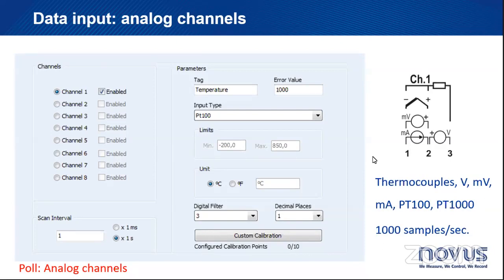Well, there are some cases where you really want fast action and fast response time. For example, if you're measuring pressure. Pressure is something that can change very quickly and you want to act on that. So you want to see any small changes. So you might not want a big digital filter on when you're measuring pressure, for example. And mainly depending on what type of sensor you're using, okay? So digital filter is that filter which is applied by the FieldLogger, okay? Decimal places is the quantity of decimal places you want to be stored and displayed, okay? Let's go to the next example here.